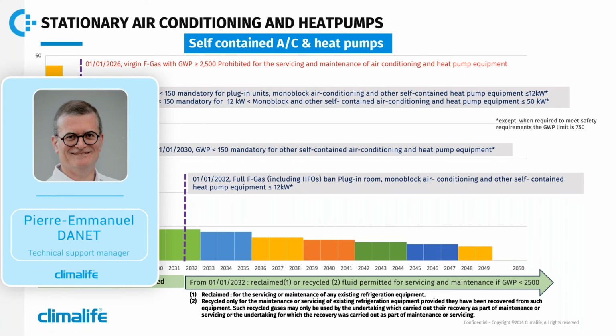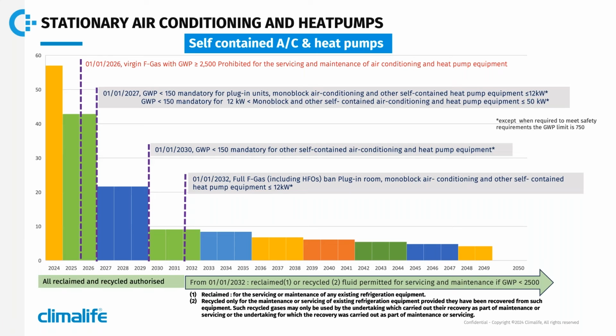Yes, Delphine. What is new with the air conditioning and fixed heat pump sectors? From January 1st, 2026, it will be forbidden to use virgin refrigerants with a GWP more than 2,500 for the maintenance of installations. From January 1st, 2027, we must use a refrigerant with a GWP less than 150 for plug-in units, self-contained air conditioners, or heat pumps of less than 12 kilowatt. And for packaged air conditioners or self-contained equipment and heat pumps up to 50 kilowatt, we have the same obligation. From January 1st, 2030, a GWP of less than 150 will be mandatory for all standalone equipment and heat pumps except for safety requirements. These safety requirements have yet to be defined.